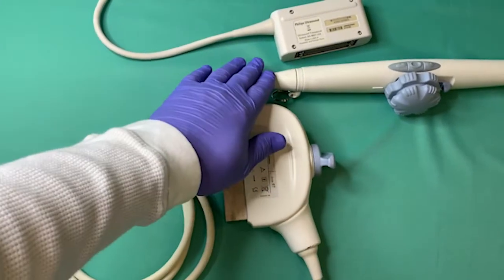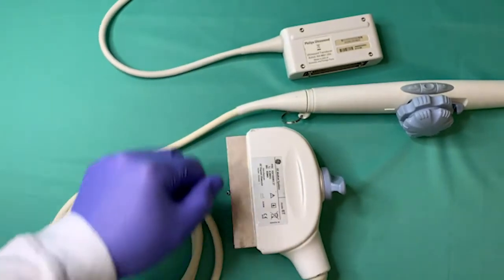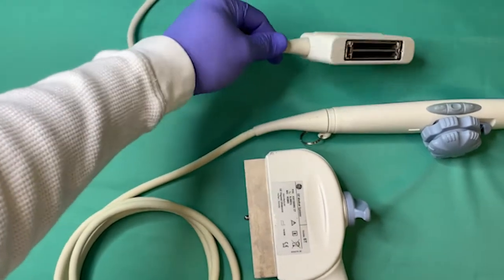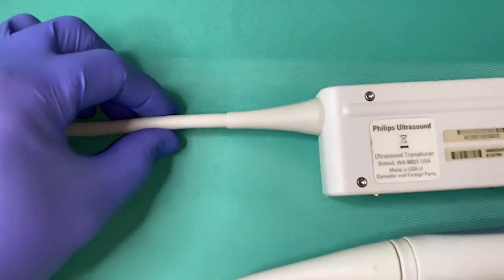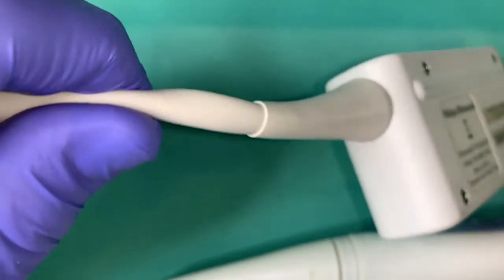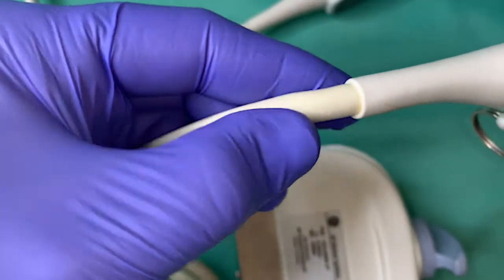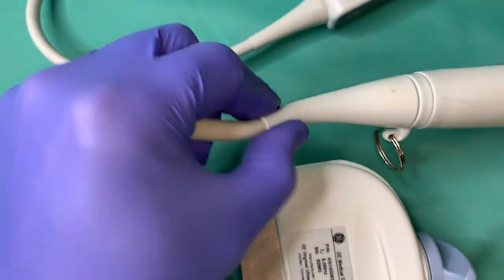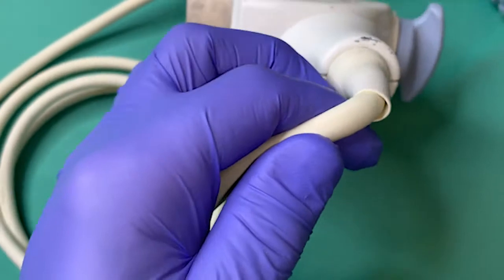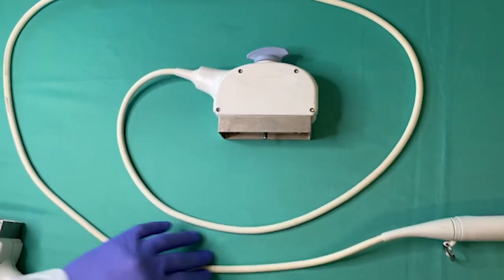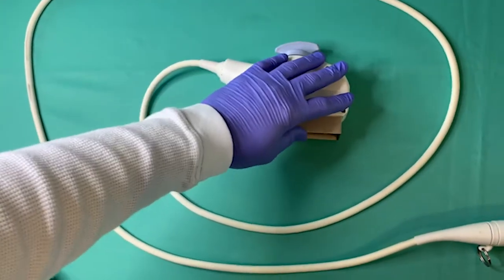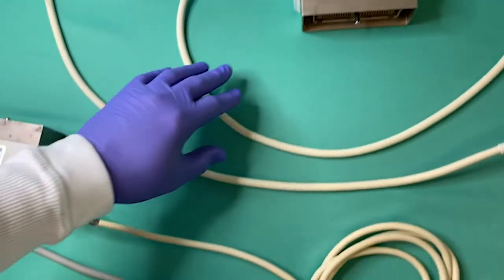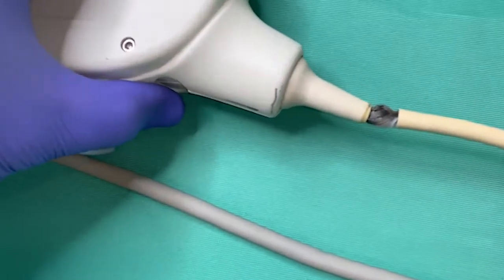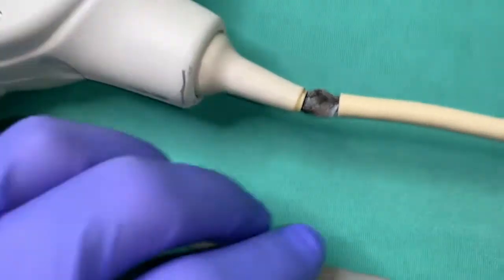Strain reliefs are located at either end of the system cable, and they should be very flexible. The strain relief itself may or may not be sealed to the cable sheathing based on the specific OEM design. Inspect each strain relief for any cuts, tears, or any other kind of mechanical damage. The system cable spans the distance between the system connector and the control body. It should not possess any cuts, tears, or heavy abrasions.